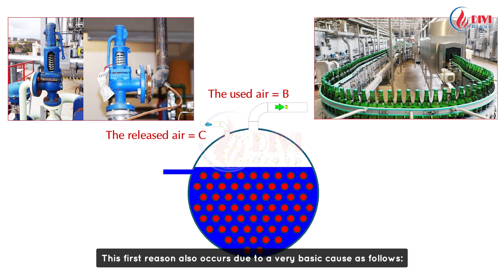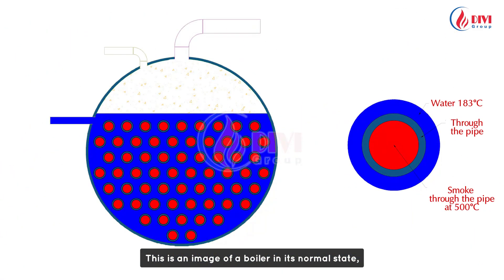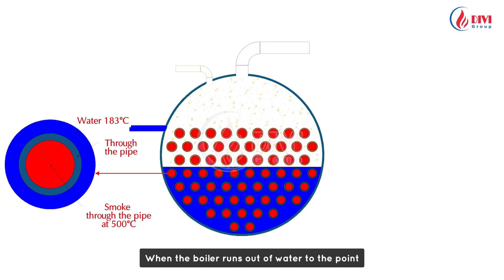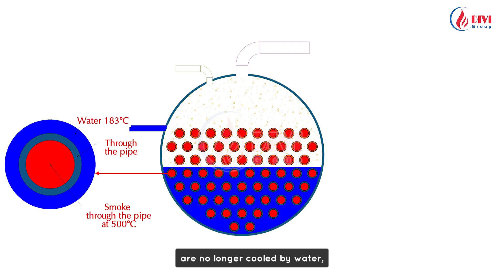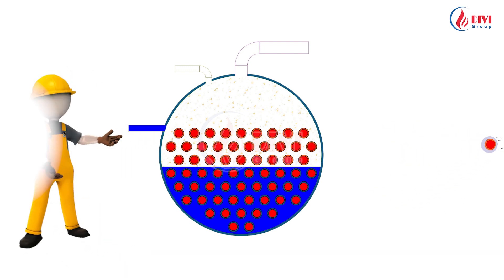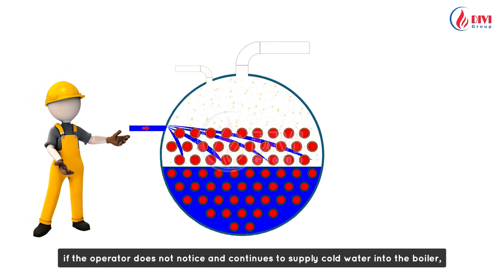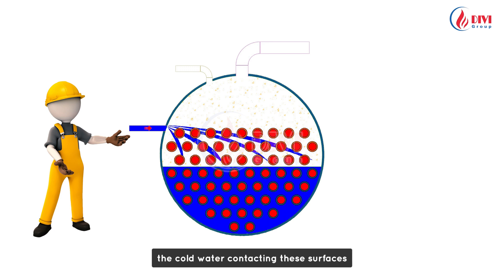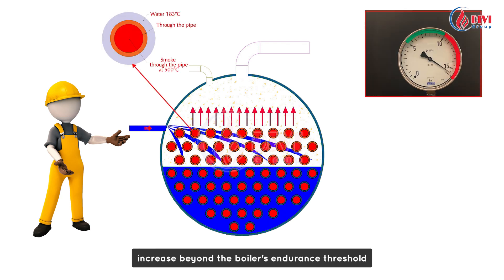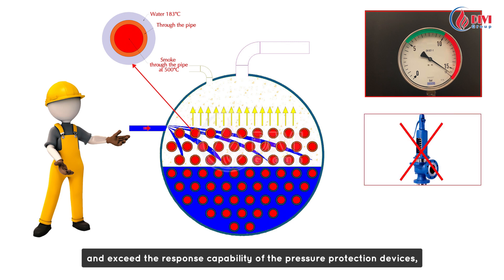This first reason also occurs due to a very basic cause. In the normal state, the boiler's fire tubes are submerged in water with smoke traveling inside the tubes. The tube walls are always cooled by water, so their temperature stays close to the water temperature, even though the smoke flow temperature is high. When the boiler runs out of water and the steam-generating steel tubes are no longer submerged, their temperature rises to nearly the smoke or flame temperature. If the operator does not notice and continues to supply cold water into the boiler, the cold water contacting these hot surfaces will instantly transform into steam at a very high rate, causing the pressure to quickly exceed the boiler's endurance threshold and overwhelm the pressure protection devices, leading to a boiler explosion.